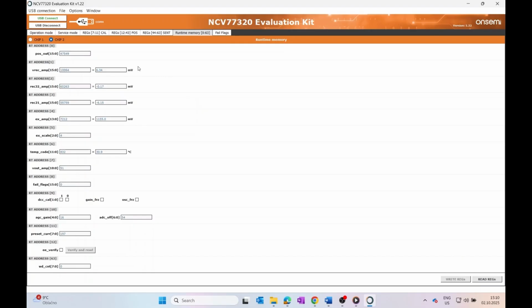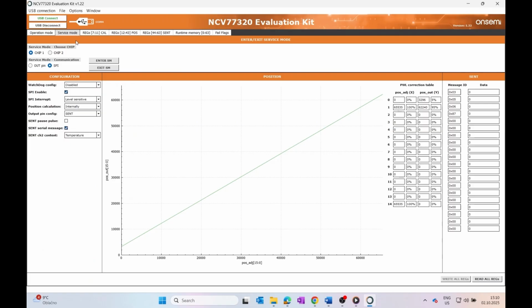These registers include the position register, overall receiver VREC amplitude, which should range between 4 to 100 millivolts according to the datasheet, differential input amplitudes, excitation coil amplitude, device temperature, and preset current. The preset current should not be saturated at the maximum value of 255, as this would indicate low inductance in the excitation coil, preventing the sensor from driving sufficient amplitude. Although the sensors are pre-calibrated, you can perform the calibration manually, especially if you're using a custom sensor.